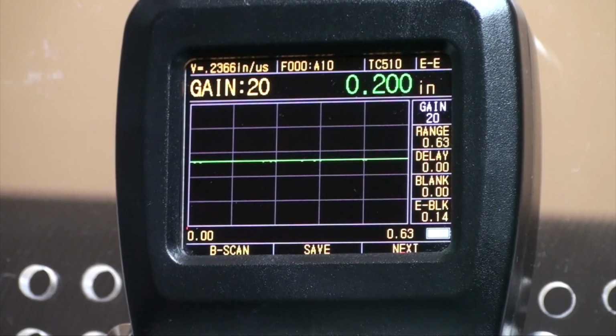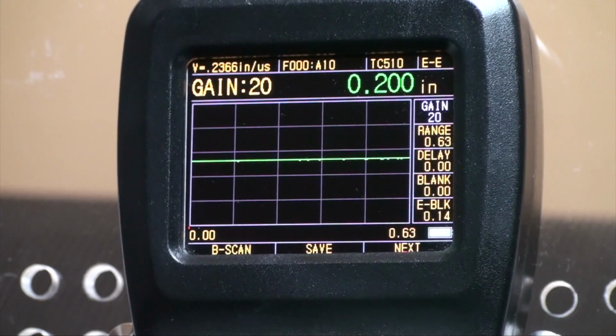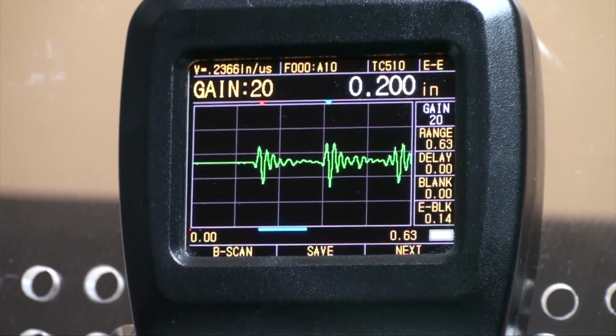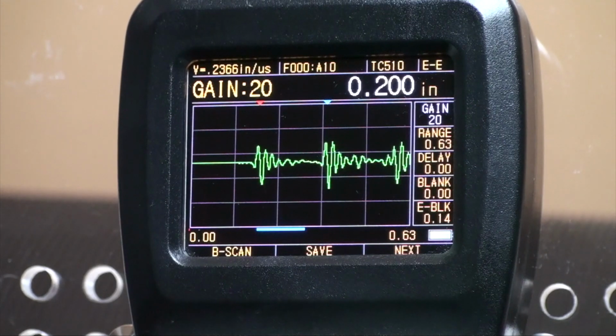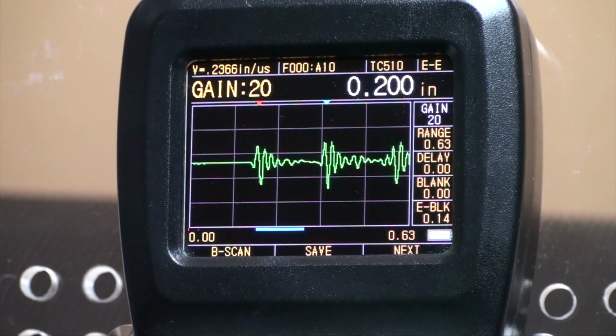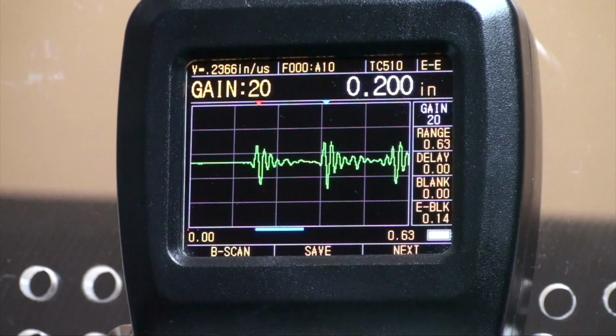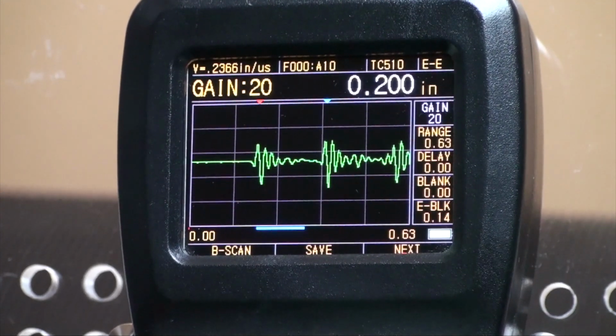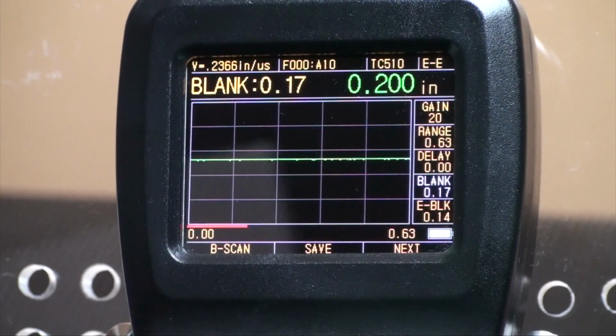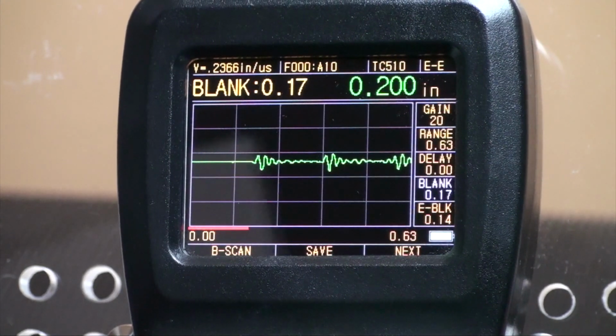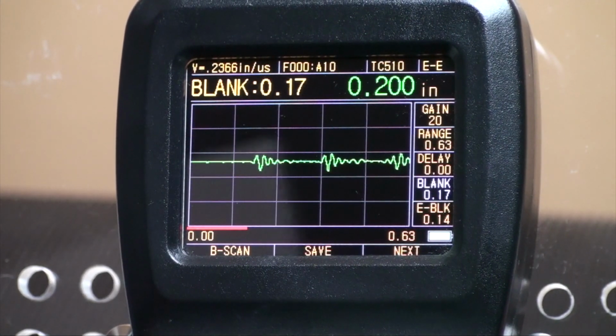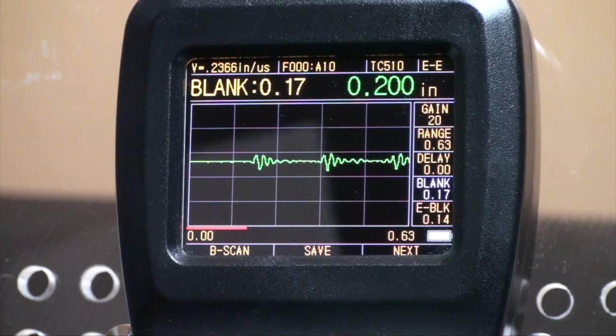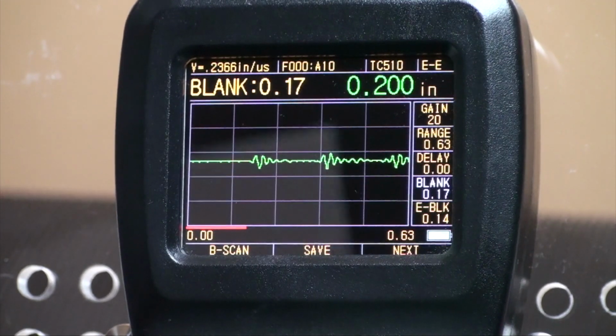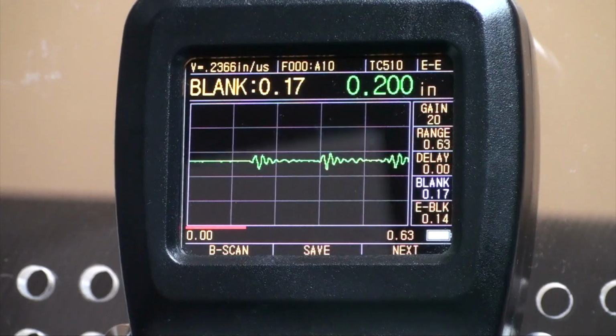When in echo to echo mode, the red arrow on the screen should point to the first wave. The blue arrow should point to the second wave. This tells you that you have the gain set correctly. In standard mode, only the red arrow will show. Blanking hides the unnecessary and useless clutter in front of the main waves. Incorrect readings can be caused by material issues such as corrosion, internal material defects, or even a specific material such as aluminum. Only adjustments in the gain can solve part of the problem.